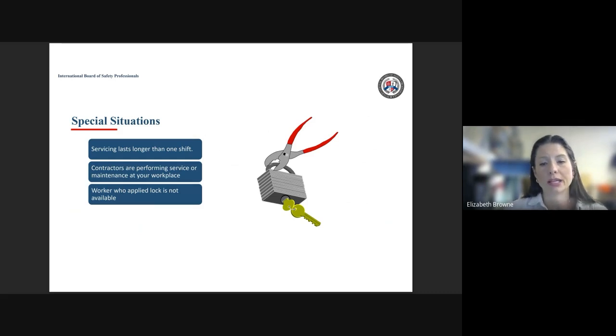And if a worker who applied a lock is not available, but we're ready to restart the equipment, you must have a procedure specific to your workplace on how you are going to confirm that the worker is in fact not still working on the equipment. So typically companies will develop a form where a supervisor must make an attempt to contact that employee at least 2 times. Sometimes employees have emergencies and they have to leave work and they forget to take the lock off.